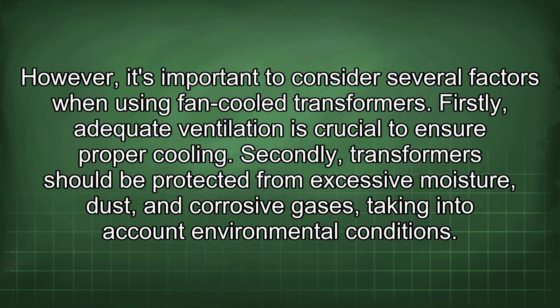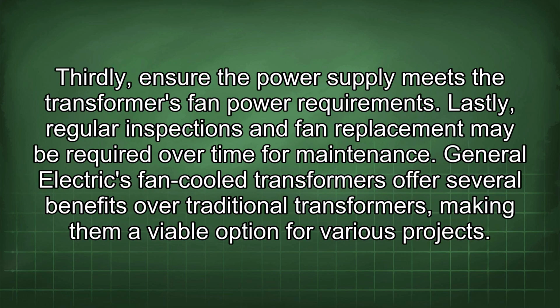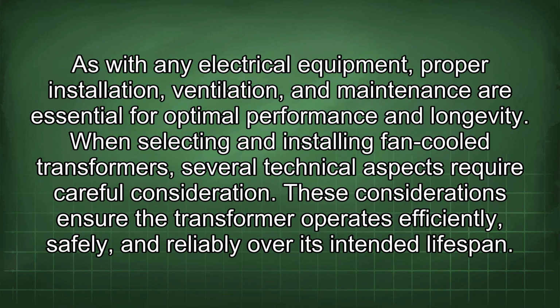However, it's important to consider several factors when using fan-cooled transformers. Firstly, adequate ventilation is crucial to ensure proper cooling. Secondly, transformers should be protected from excessive moisture, dust, and corrosive gases, taking into account environmental conditions. Thirdly, ensure the power supply meets the transformer's fan power requirements. Lastly, regular inspections and fan replacement may be required over time for maintenance. General Electric's fan-cooled transformers offer several benefits over traditional transformers, making them a viable option for various projects. As with any electrical equipment, proper installation, ventilation, and maintenance are essential for optimal performance and longevity.